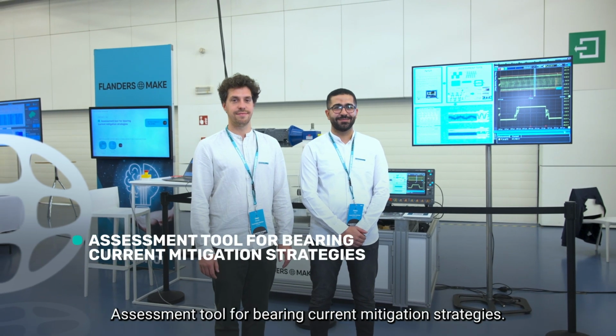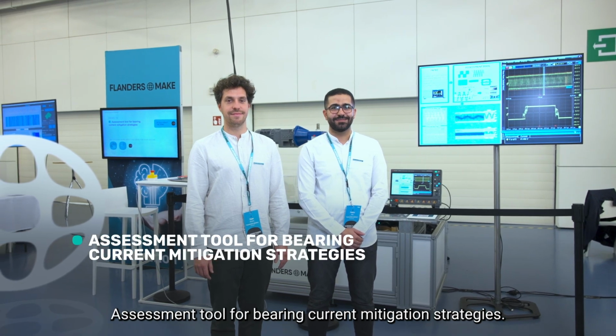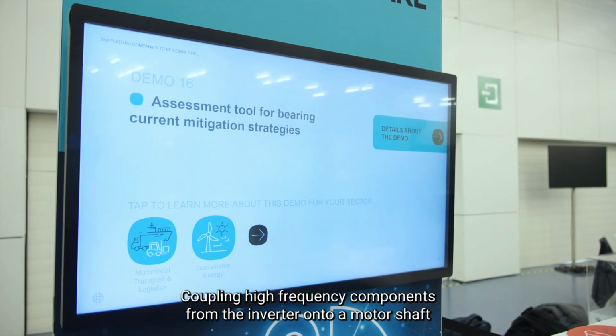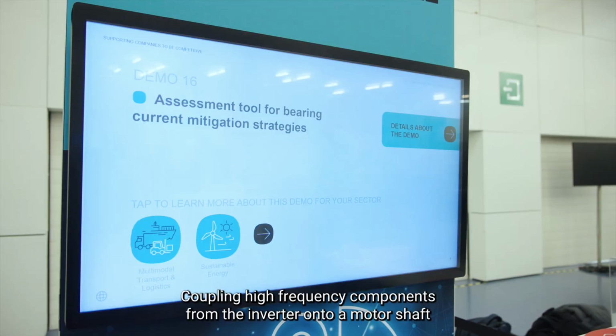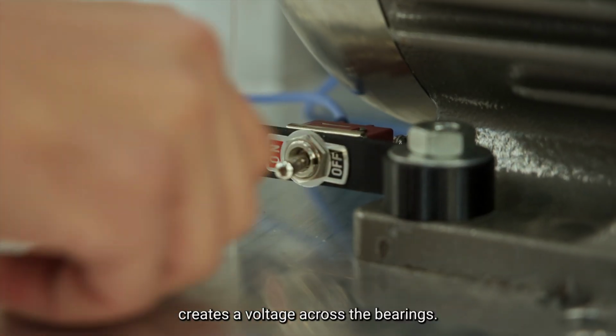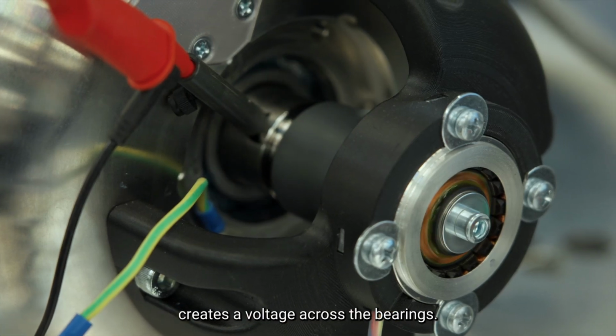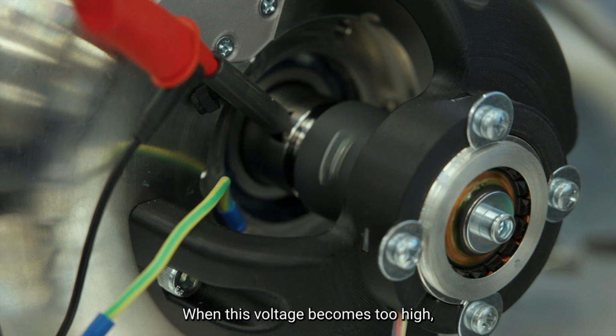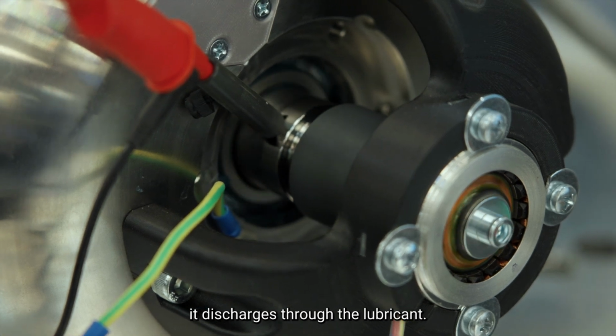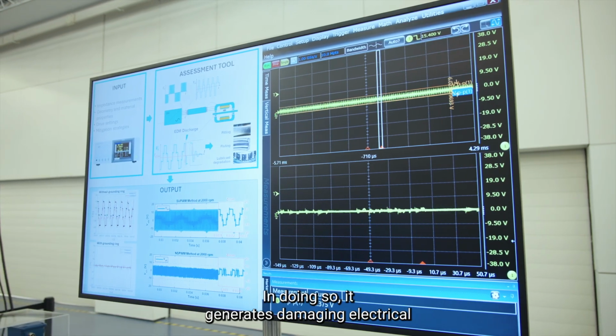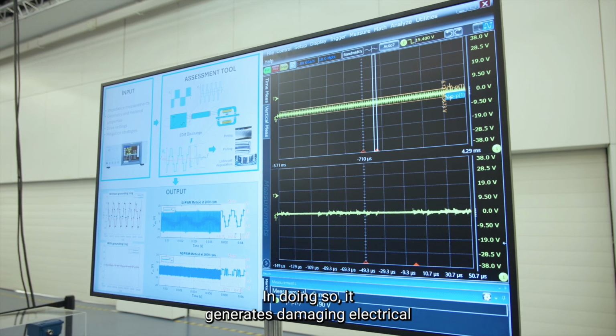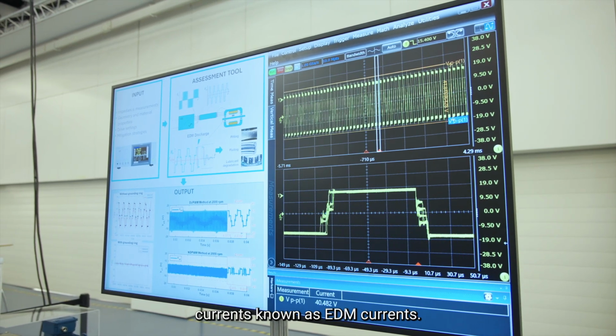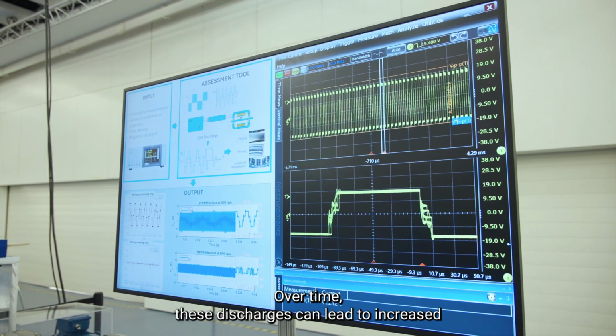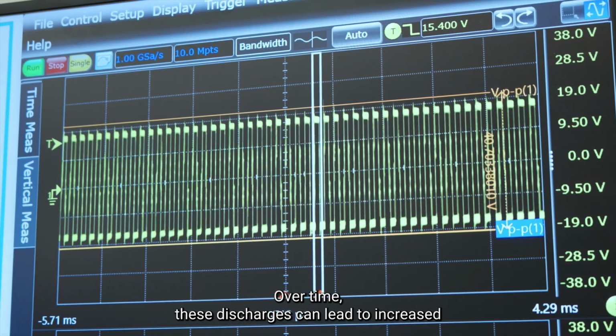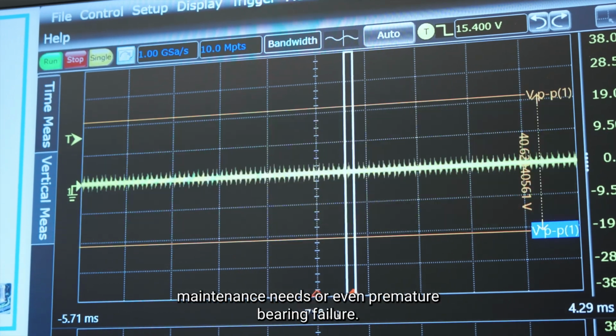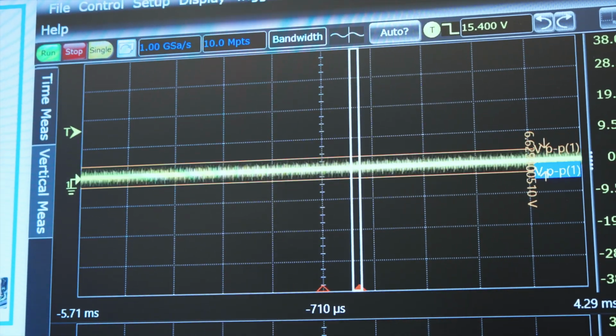Assessment tool for bearing current mitigation strategies. Coupling high-frequency components from the inverter onto a motor shaft creates a voltage across the bearings. When this voltage becomes too high, it discharges through the lubricant. In doing so, it generates damaging electrical currents known as EDM currents. Over time, these discharges can lead to increased maintenance needs or even premature bearing failure.